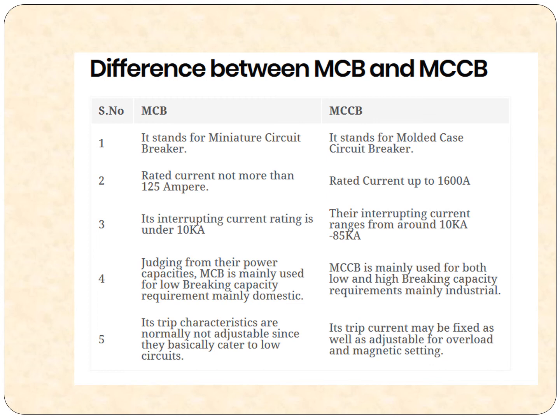Judging from their power capabilities, MCB is mainly used for low breaking capacity circuits, that is, domestic applications. MCCB is for industrial applications. MCB has a tripping characteristic that is normally not adjustable. MCCB has adjustable trip characteristics for overload and magnetic settings.